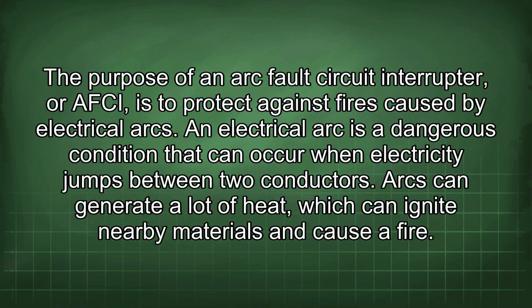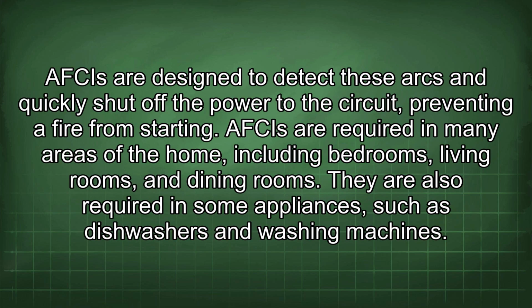The purpose of an arc fault circuit interrupter, or AFCI, is to protect against fires caused by electrical arcs. An electrical arc is a dangerous condition that can occur when electricity jumps between two conductors. Arcs can generate a lot of heat, which can ignite nearby materials and cause a fire. AFCIs are designed to detect these arcs and quickly shut off the power to the circuit, preventing a fire from starting. AFCIs are required in many areas of the home, including bedrooms, living rooms, and dining rooms. They are also required in some appliances, such as dishwashers and washing machines.